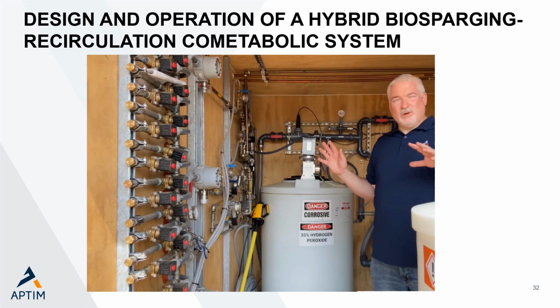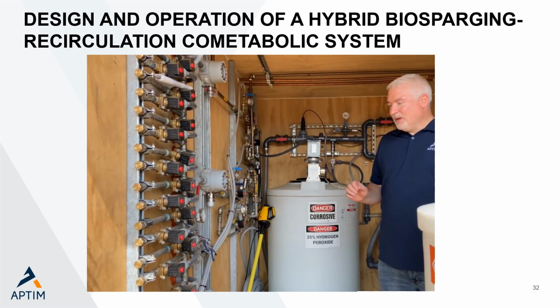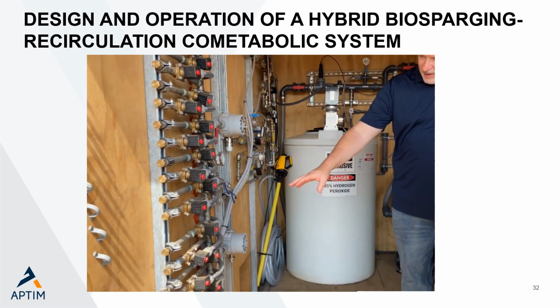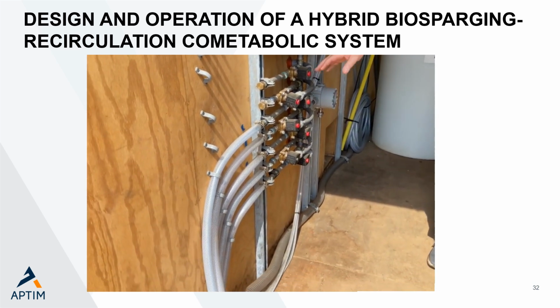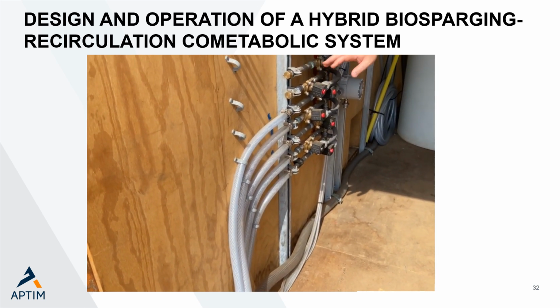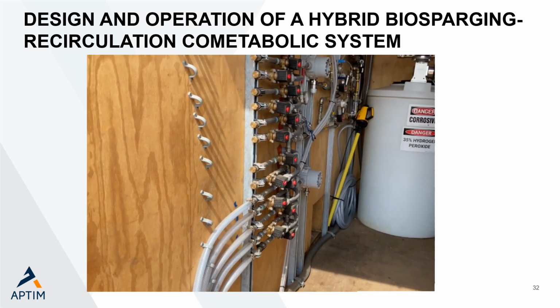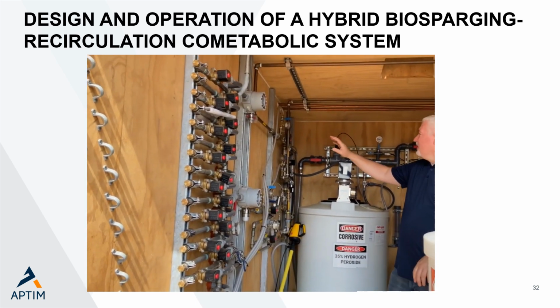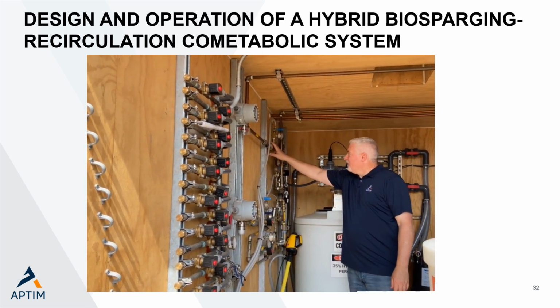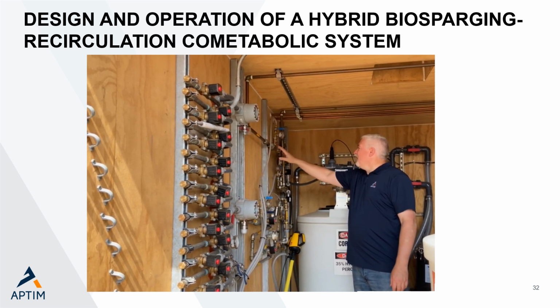On this project, we're only adding the oxygen to 5 of the wells. You can see those at the bottom here, and the solenoid valves that control the flow to each of these individual wells. The oxygen comes from this side of the Connex box across the ceiling, goes through a flashback arrestor, which is a safety feature.